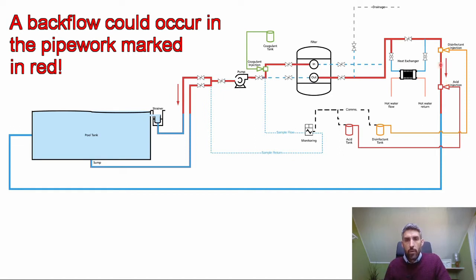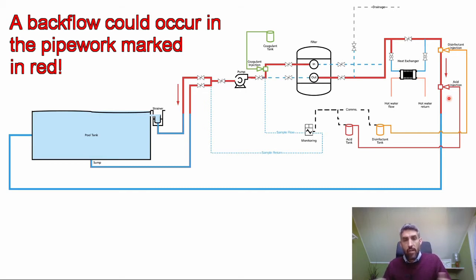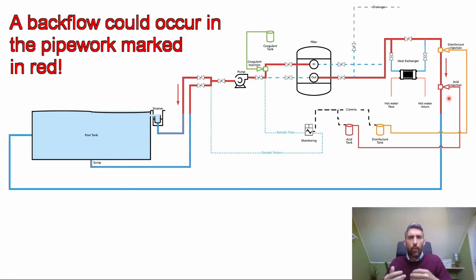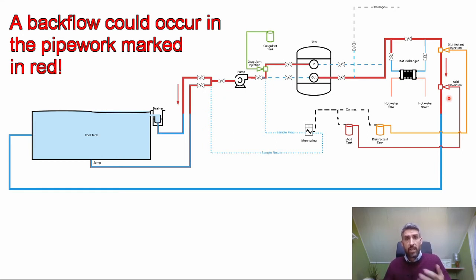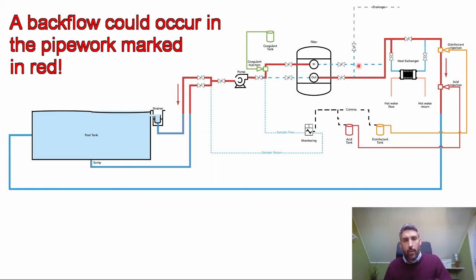You've got your disinfection injection point there and your acid injection point there. On this schematic, they're both downstream of the filtration system. So what could happen is when you mix that disinfection substance with the acid pH correctant substance, you're going to get a reaction that creates chlorine gas. That chlorine gas could just sit there until you re-establish the power supply to the pump, and then this toxic noxious gas gets pushed all the way through into the pool.